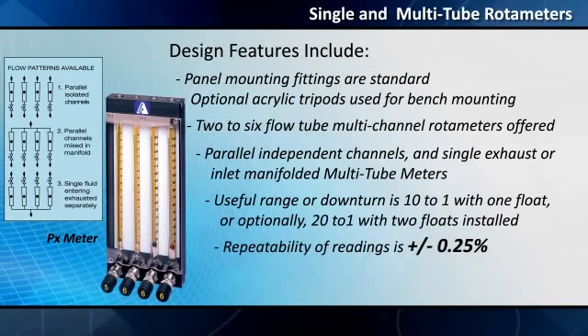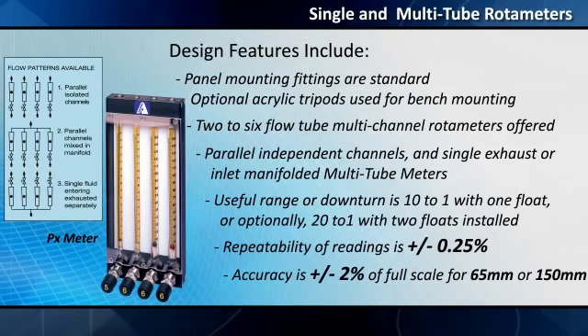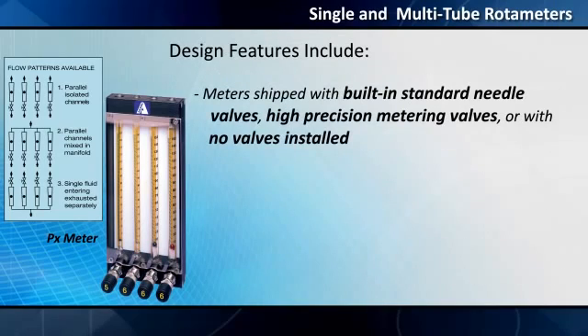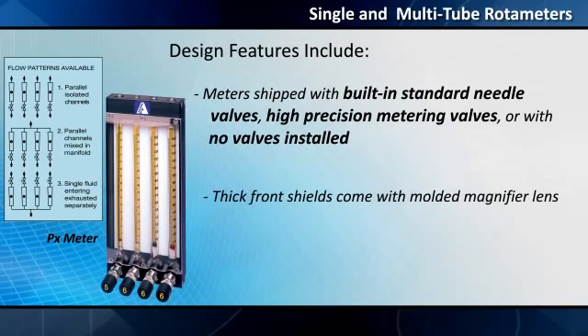Repeatability of readings is plus or minus 0.25%. Accuracy is plus or minus 2% of full scale for 65 mm or 150 mm, and plus or minus 5% of full scale for direct reading meters. Meters are shipped with built-in standard needle valves, high-precision metering valves, or with no valves installed. Thick front shields come with molded magnifier lens.